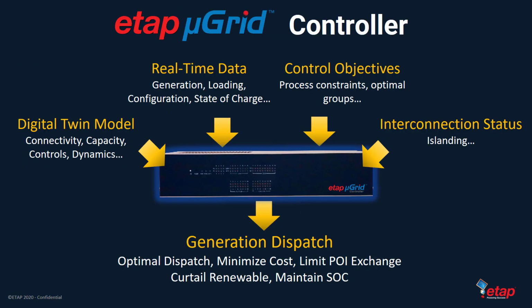Another controller is the microgrid controller. The microgrid controller performs generation dispatch, black start management, islanding, and reconnection management of the microgrid. Using the digital twin model, the controller can be validated in ETAP as well as performance of the microgrid, and then logic downloaded to the microgrid controller, performing software in the loop and hardware in the loop testing within the same system.